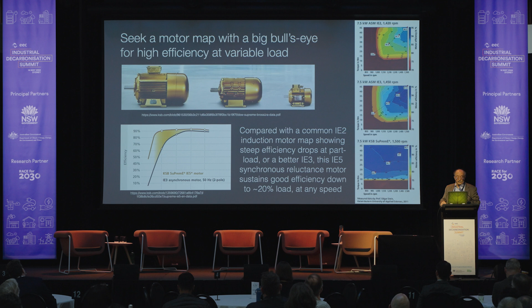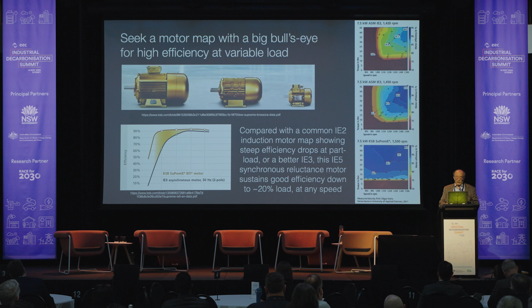So the gold zone in the lower left map shows the energy savable at part load by running that 7.5 kilowatt model rather than a normal IE3 like the one in the middle map on the right. And the advantage captured by the gold zone can easily be an extra 10 or 20 percentage points beyond the roughly 5 points you'd expect from just going to an IE5 motor. Here's a graph showing the same issue over about a 500x range of motor size. I won't elaborate it here, but the point is that the more efficient your motor gets, the flatter an efficiency curve it's likely to have across load.